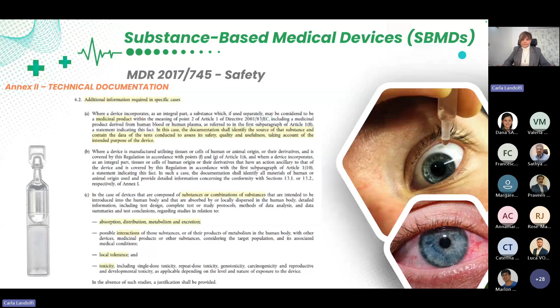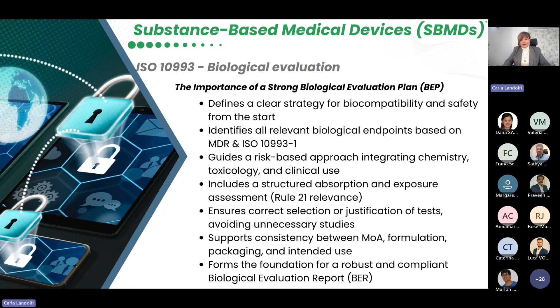Before closing, I'd like to highlight the importance of the biological evaluation plan, because this is really the foundation of a compliant and scientifically sound assessment. A well-designed BEP prevents unnecessary testing, ensures that the formulation, packaging, and overall risk profile are fully aligned with MDR and ISO expectations, and ultimately guides the entire process toward a complete and defensible biological evaluation report.